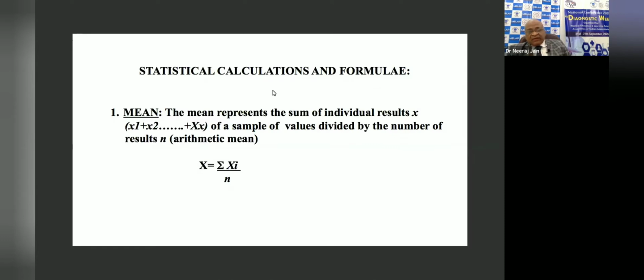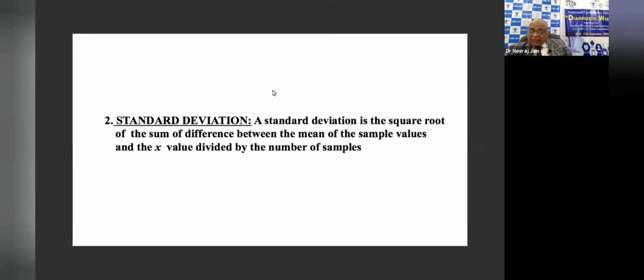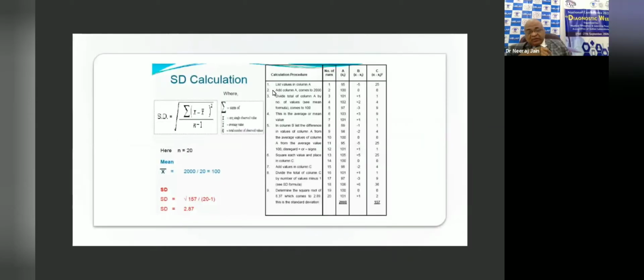Now we are calculating our own mean, but we also have to understand there is no significant variation in our day-to-day testing. For this, what is the statistical tool we have? Standard deviation. It is also provided to us by the manufacturer. We have to ensure our calculated standard deviation is not wider than the manufacturer standard deviation, and our calculated mean is within one standard deviation of the manufacturer mean. So we have two statistical tools.